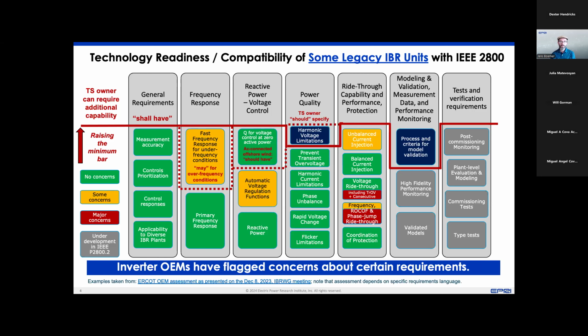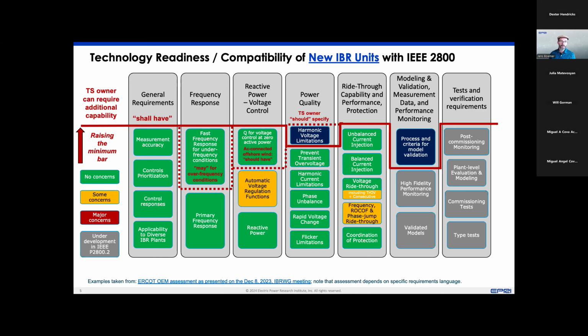Now, when we look at the new IBR units, then the picture looks a little bit more optimistic. We do expect most of the new and compatible 2800 inverters to be capable of injecting unbalanced current during the fault. But there are still some challenges related to the transient overvoltage and the consecutive voltage ride-through, as we heard today, and some related to rate-of-change-of-frequency or phase angle jump ride-through.